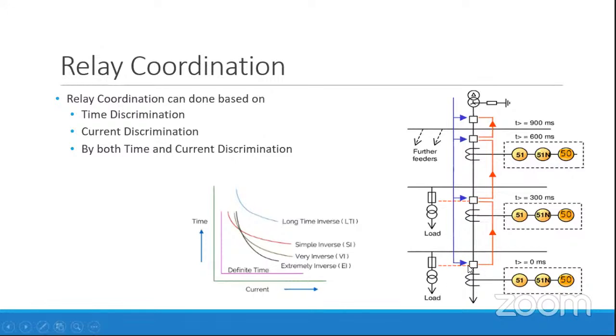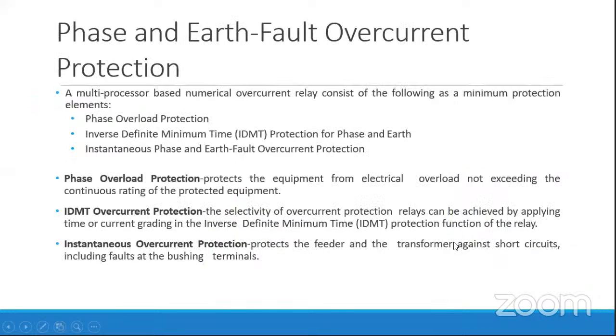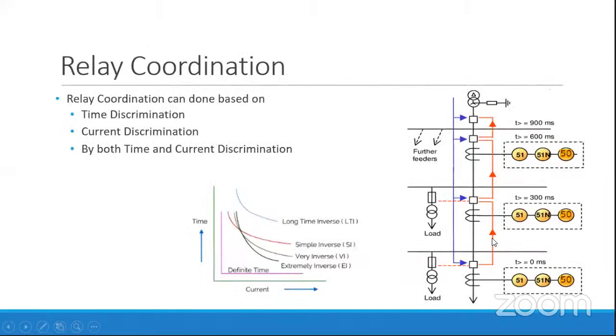So the discrimination should be based on current, such that this breaker isolates with minimum time and minimum current. If the current gets beyond a certain value which is set for this breaker, then only this breaker should operate. And if this breaker or this relay also fails to operate, then and only then this one should operate, and the current will be higher at this particular location.